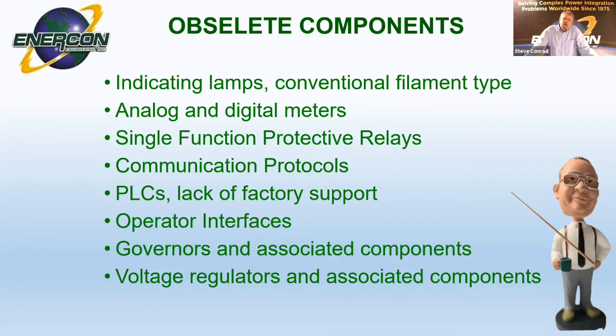Communication protocols change. Some PLC manufacturers used to have proprietary protocols, and a lot of that has changed. Ethernet is probably the most common protocol used today. Some older protocols can't communicate with these older devices. A lot of the PLCs that are obsolete, you can't buy them, and you certainly won't get factory support because they don't make them anymore.